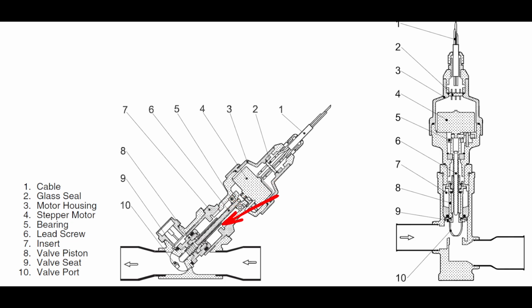Now, something to understand here. These valves in their makeup, this is a threaded assembly in here. And these are typically made of Teflon. Now, the actual stem coming off of the motor may be a stainless steel or a steel shaft of some kind, but the actual threading piece that's attached to the plunger will typically be a Teflon thread.